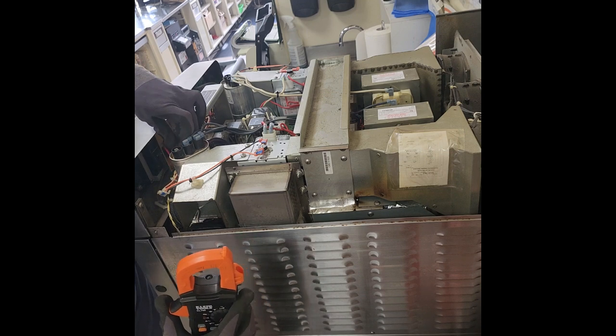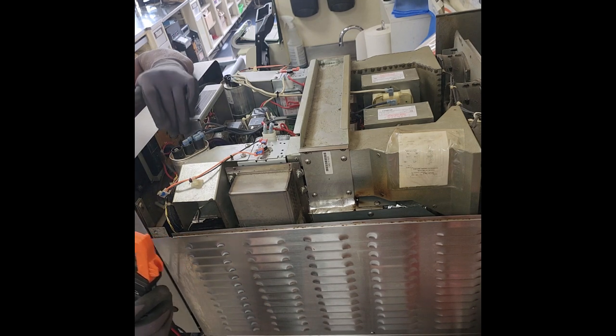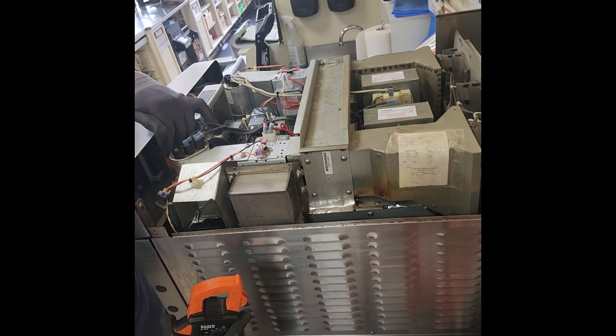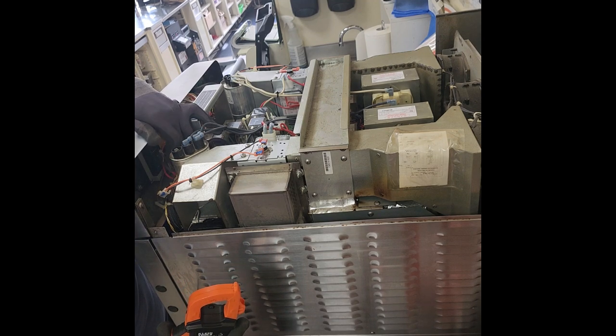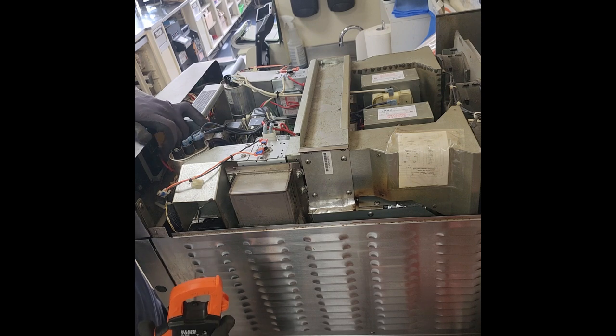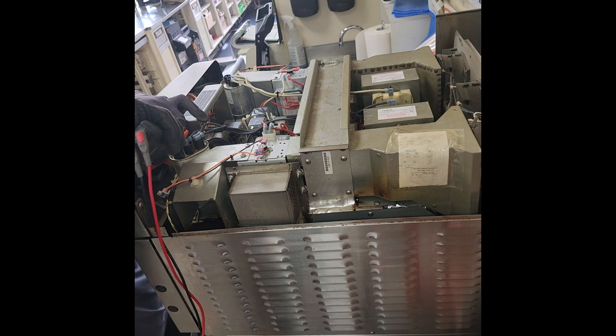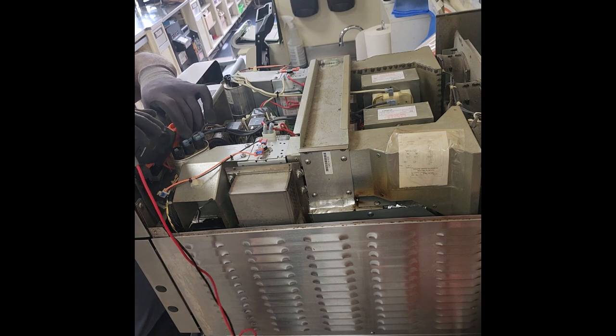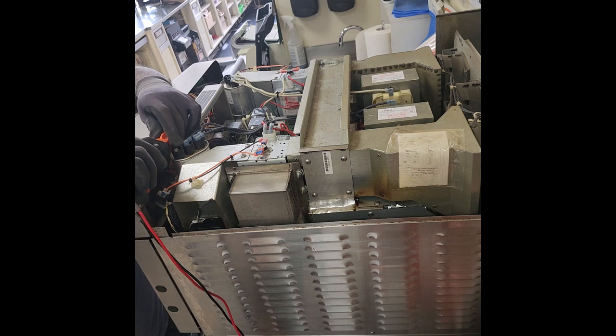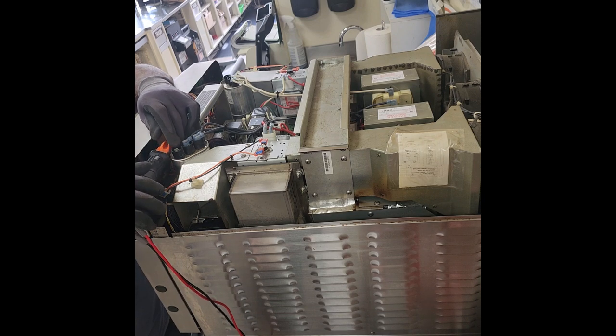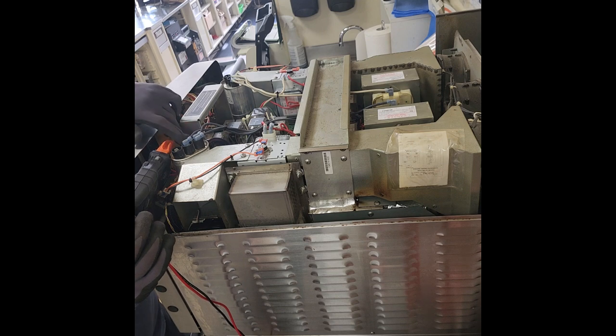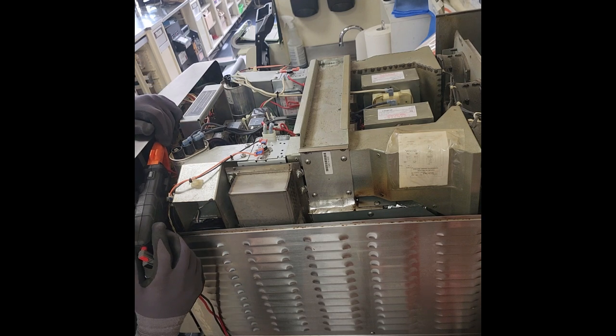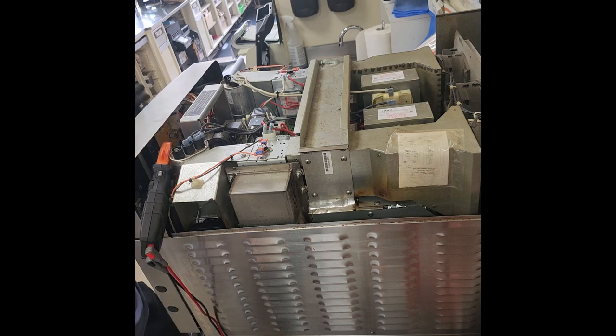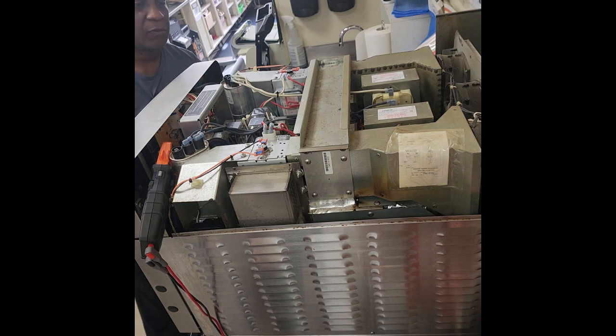Hey, you're probably not going to be able to see it very well, but the amp draw wire is down here. It's a red wire and it goes through the CT loop, so I'm just going to put my amp clamp around that. It's kind of tucked down on the side, and I've got my meter on the amps, so once I power it up I'll be able to go ahead and test that. Looks like we're ready to go.